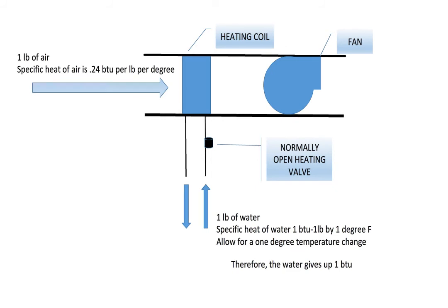At the same time, we will pass one pound of air across the coil. The specific heat of air is 0.24. That is, it takes 0.24 BTU to change the temperature of one pound of air by one degree Fahrenheit. 0.24 BTU is very close to a quarter of a BTU.